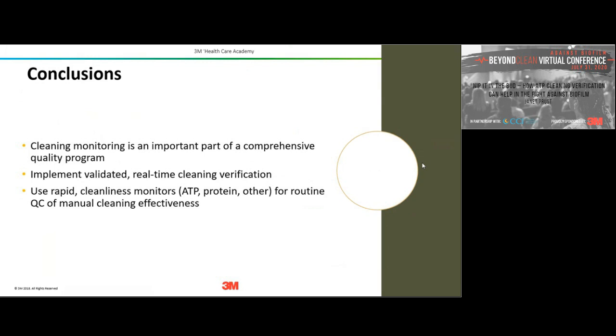Q&A: How many CFU do you need for the ATP system to detect? ATP is not detecting CFU — it's detecting overall clinical soil. There have been studies showing you can have very low levels of CFU below the ATP system's detection threshold. And there have also been situations with extremely high CFU levels where the ATP test came back and passed. ATP is simply not measuring specific CFU — keep in mind, it measures total organic soil, not individual microbial counts.